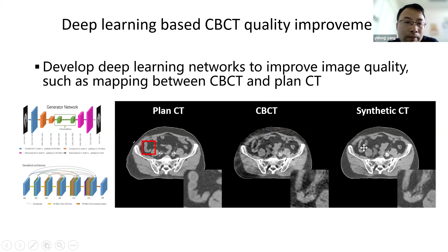After we improve the image quality of cone beam CT, we can expand its functionality. Before, we could only use cone beam CT for patient positioning during radiation delivery. Now we have better signal-to-noise ratio and better contrast. We can use cone beam CT for target contouring and OAR contouring. And because the accuracy of the CT number is improved, we can also rely on cone beam CT for dose calculation. So now we have expanded its functionality from positioning to treatment planning.